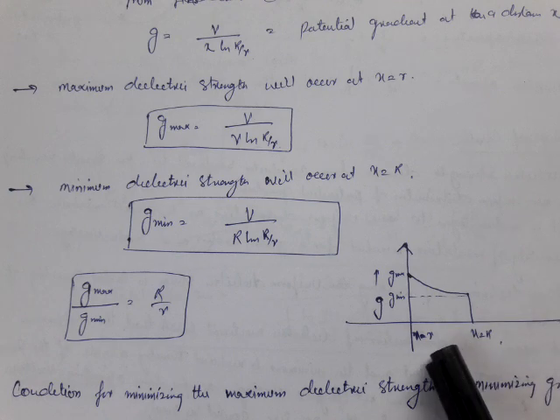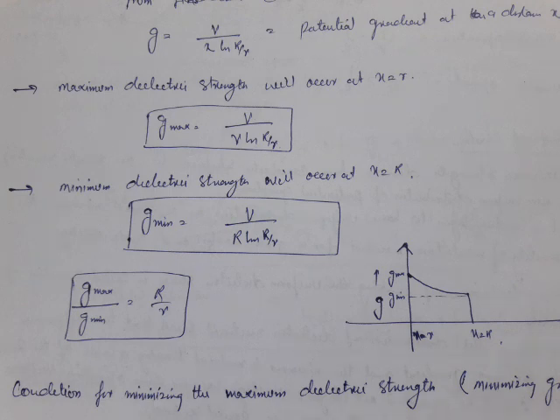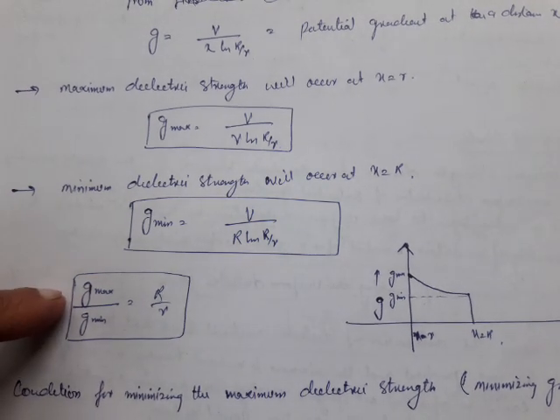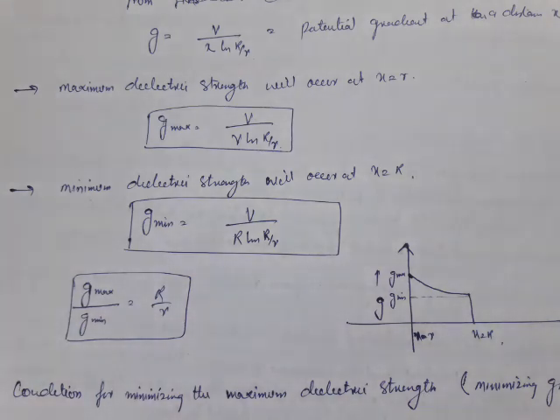This is the variation of electrical stress from the surface of the conductor to the sheath — the variation along the dielectric. Just as we see potential distribution along an insulator string from conductor to tower, here we see the potential distribution in the dielectric from the conductor surface to the inner radius of the sheath. The ratio G_max to G_min equals R divided by r.